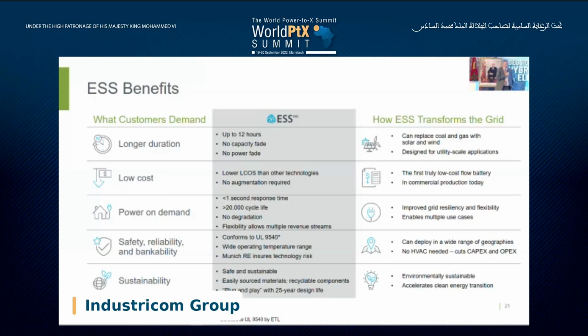The technology has a very low levelized cost of storage simply because iron is cheap, and cheapness is a key parameter as we discussed before. One thing unusual for a flow battery is that it's a fast response system—so if you're building microgrids, which I wholeheartedly agree is one interesting thing to do, a 12-hour ESS battery can also do frequency and voltage regulation inside the system. Another interesting thing about a flow battery is that it's not a closed loop system, it's an open system, which means if you worry about chemical changes accumulating over time to degrade the system, you can do something about it. That's exactly what a lot of ESS's intellectual property is about—how you keep the electrolyte conditioned so you have no capacity fade, no power fade, and no energy losses over time at all.